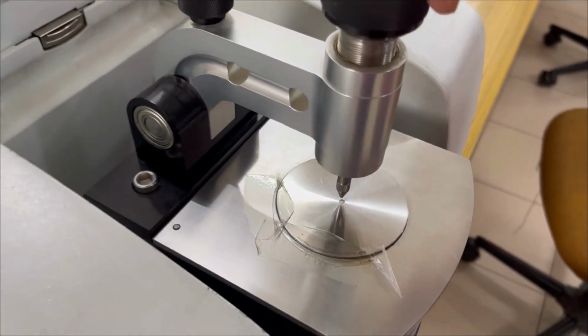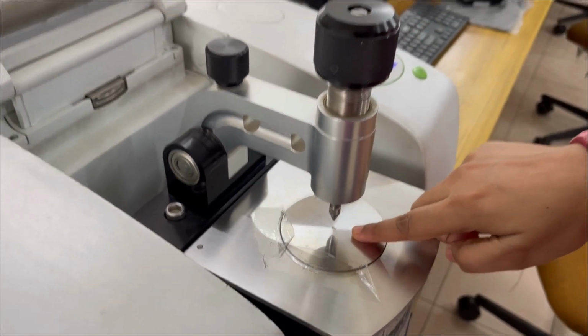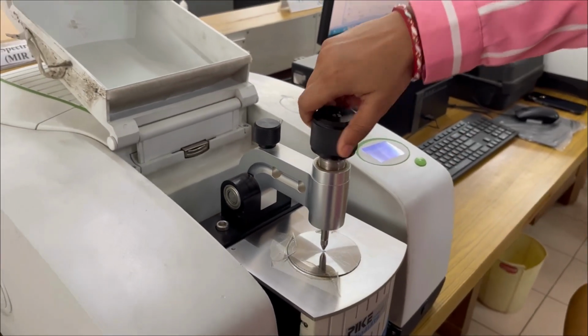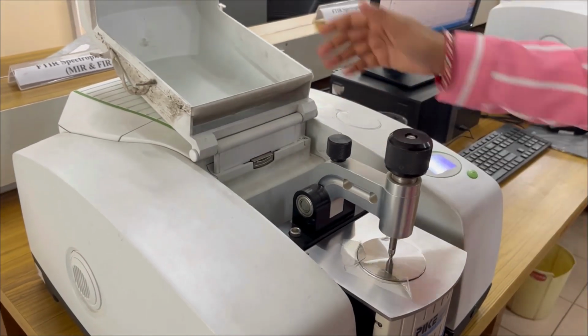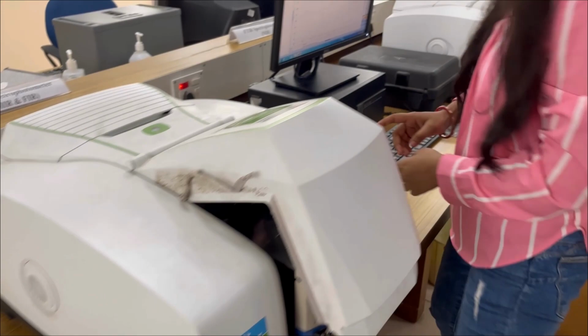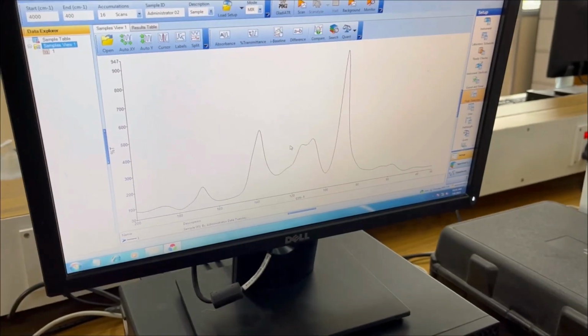Any solid or liquid sample can be analyzed in this instrument. Here we keep the sample on the germanium crystal and the probe detects the sample. Various peaks are observed in the result obtained.